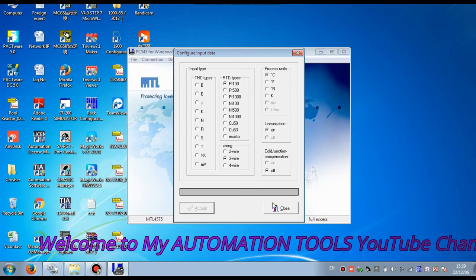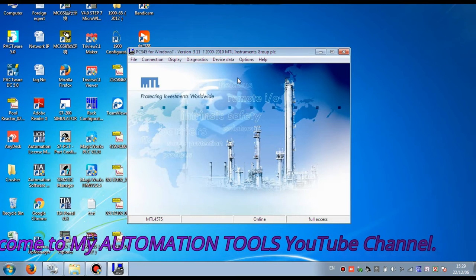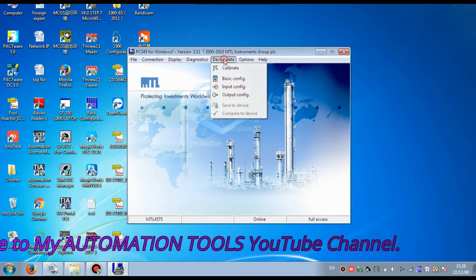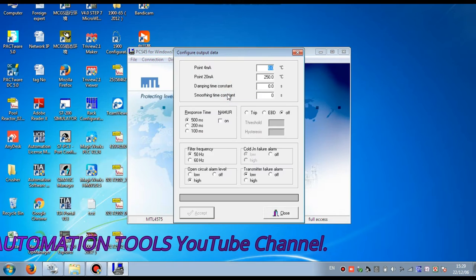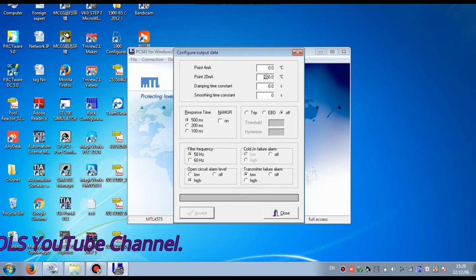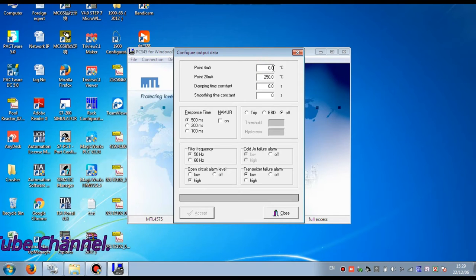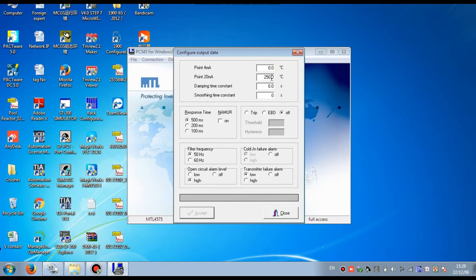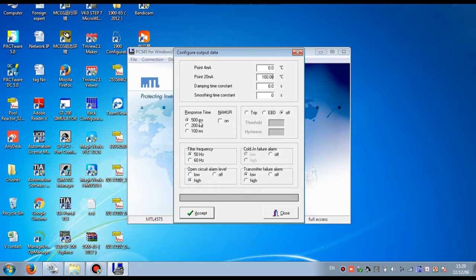Press Close, then again go to Device Data and press Output Configuration. Here you can set the range of this transmitter. Our transmitter needs 0 to 100 degrees Celsius, so we press 0 to 100. The output formula is showing 4mA at 0 and 20mA at the upper range.